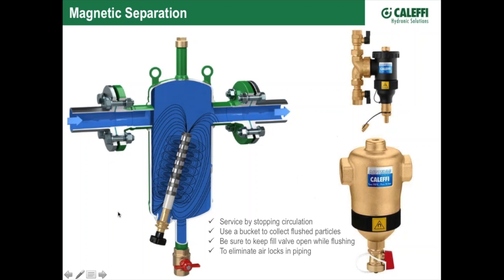So then we had the challenge of saying, well, what are we going to do on our welded steel vessels? We just can't put a magnetic band around the outside of that. The whole thing will turn into a magnet. That wouldn't work so well. So the solution that we came up with here is we said, well, let's put a dry well in there, a brass dry well in there, and let's put the magnets up inside that dry well.